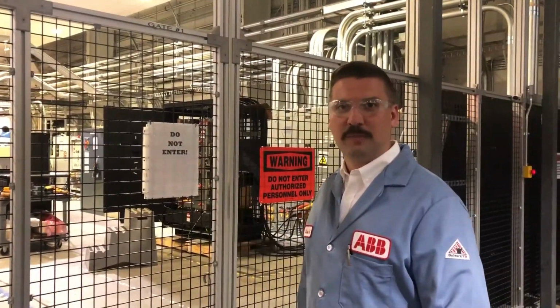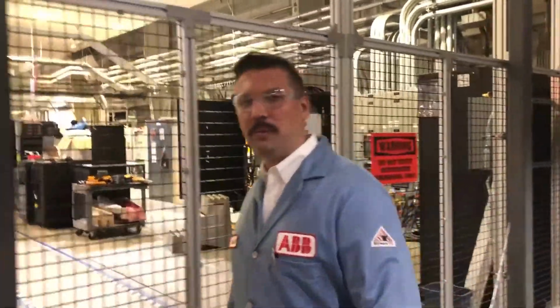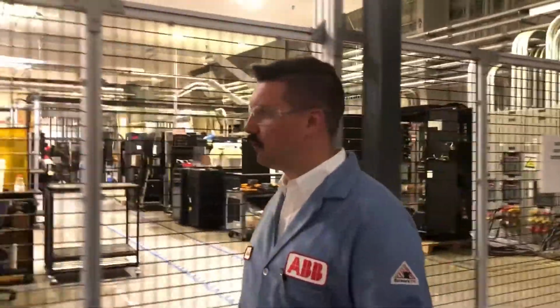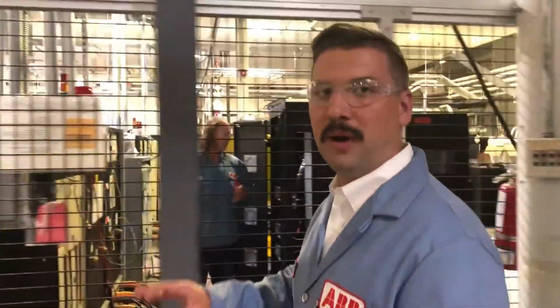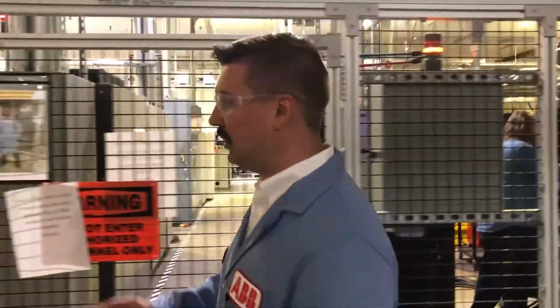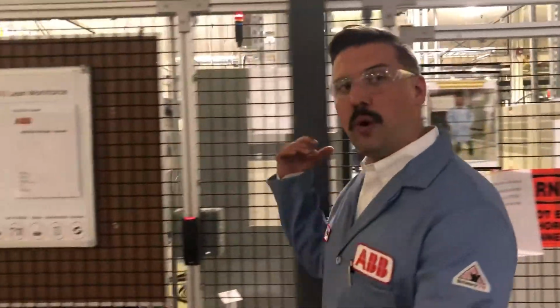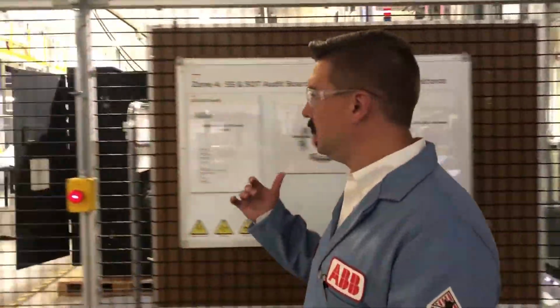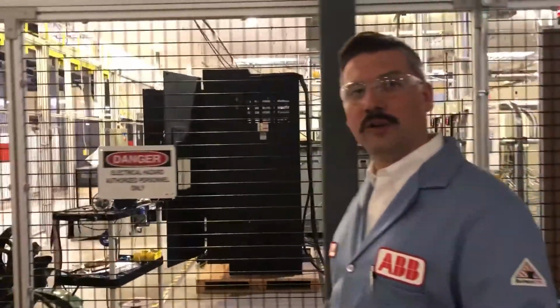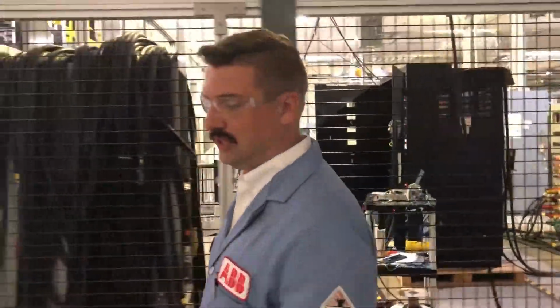Now let's transition and talk about our production test bay. Here you can see our production test space, fed by a dedicated 1.5 megawatt service entry. We have 10 test bays where we can test all products, from industrial UPS systems to static transfer switches to PDU products. We just walked past a static transfer switch, and here we can see one of our larger PDU units — a 500 kVA — going through the final test procedure.